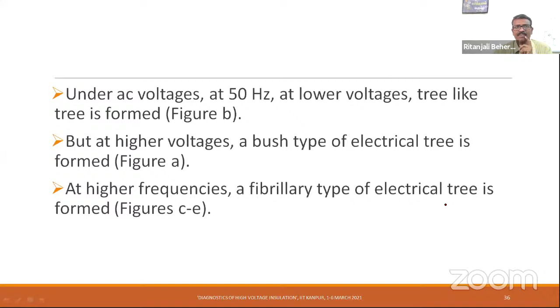So under AC voltages, which means at 50 hertz, at lower voltages, which means at 10 kV, the tree-like tree is formed. That is figure B. This one, figure B, a tree-like tree is formed. But at higher voltages, a bush type electrical tree is formed. That is A. This is at higher voltage because this is at 17 kV and this is at 10 kV.